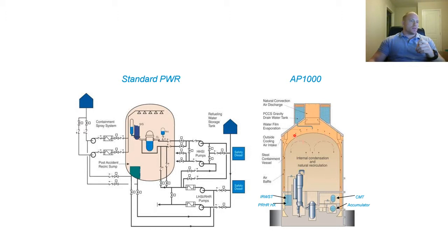So the water being sprayed over the primary containment will assist in removing that heat. It will vaporize, and then hot air rises up and out the top of the building. That creates a low pressure condition around the side, which draws in outside cool air, which goes down and around this baffle plate. That baffle plate helps this cool air drive all the way down, so it covers as much surface area as possible of the primary containment structure.